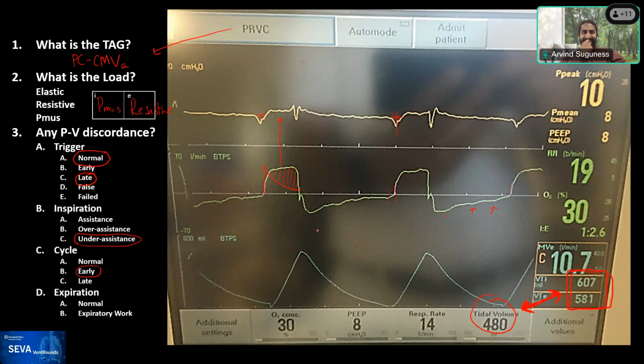Yeah, can you hear me? Yeah. It looks to me, I was actually looking at the screen when we were talking about cardiac oscillations. On the pressure waveform, that deflection at the end of inspiration looks like it could potentially be further patient effort, especially given that we contributed most of the inspiration pressure waveform to PMUS. And thank you, Dr. Mireles, for pointing out on the flow waveform that same deflection as well. To me, that looks like the patient's still trying to pull in another breath as the vent is cycling off the inspiratory cycle.